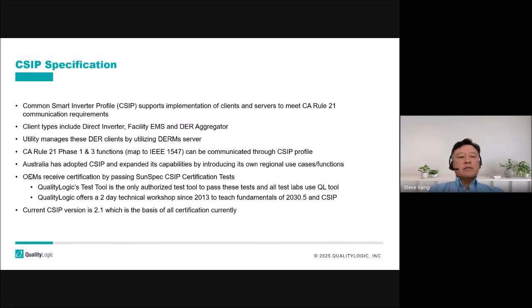In the aggregator case, all the managed inverters can be controlled by the utility server, which can potentially assign different functions and controls to individual assets, while the communication and handling is done by the aggregator itself. The utility manages the server by providing capability and controls, and the clients get those signals using the CSIP-based protocol.